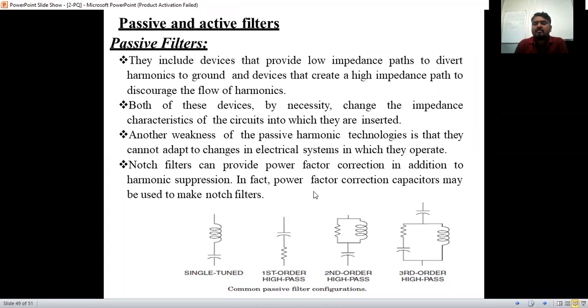In fact, power factor correction capacitors may be used to make notch filters. Wherever we use capacitor filters, we can consider them as notch filters. For harmonic distortion we use these passive filters, which are capable of both power factor correction and harmonic filtration. This is the short and sweet explanation of passive filters.